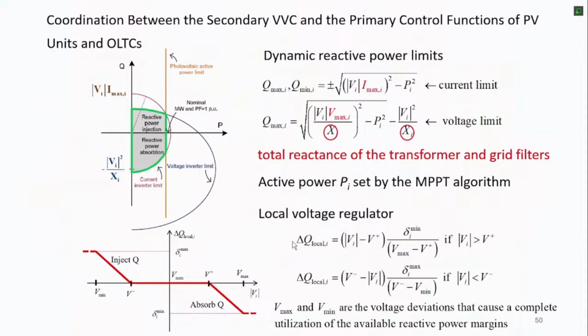So we think that the secondary voltage control, this multi-agent system, can operate when the voltage is in this range, because here it can improve the voltage after the primary control. The local control acts to compensate for the large voltage variations. So large voltage variations are for the local control, and the optimization of the voltage is for the secondary control. Is it fine? In general, the local control is faster than this mechanism because this requires some time to communicate and so on. It is also coordinated in this way with the transformer, the on-load tap changer transformer.